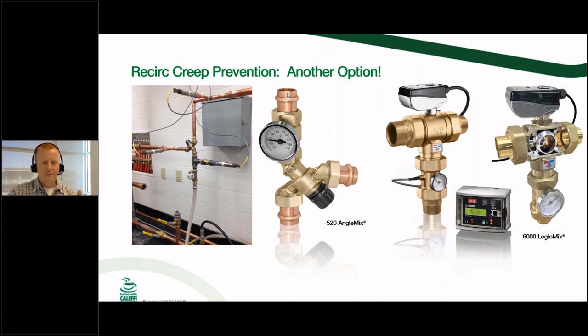Very, very cool valve. Here's just a little bit of the testing that we were doing at the lab here in Milwaukee. You'll have to forgive the black iron fittings. They're just cheaper than low lead stuff, and it's all non-potable anyways. So from there though, this guy is a good valve for, again, your smaller, your residential, light commercial applications. It's available in 1/2, 3/4, and 1-inch connections. But then if you're working in commercial applications, which is where you're probably going to see more of your continuous recirculation than your smaller residential and light commercial stuff.